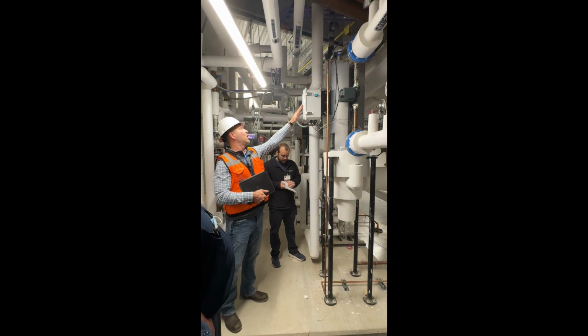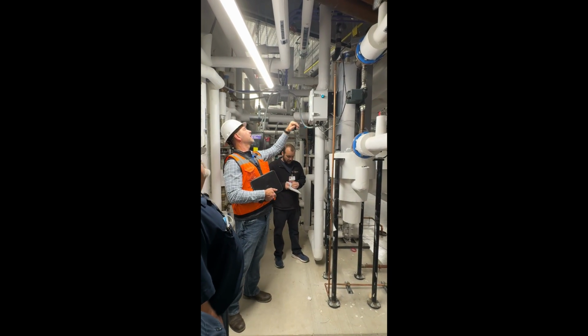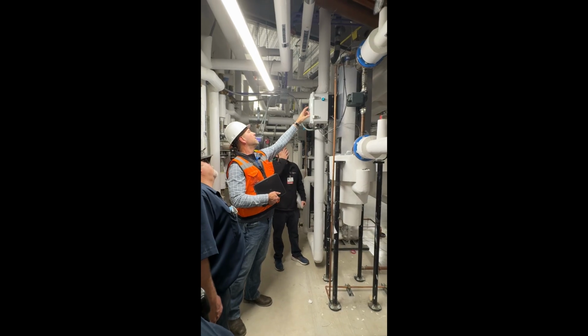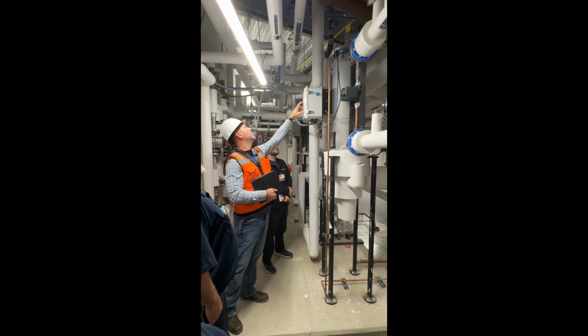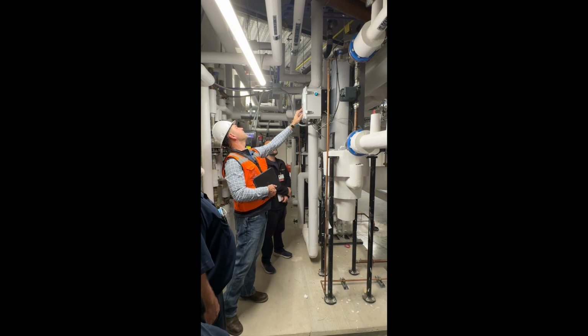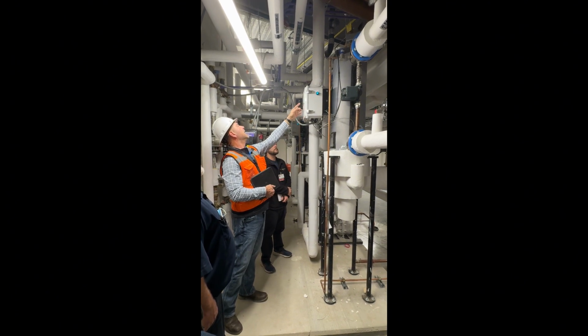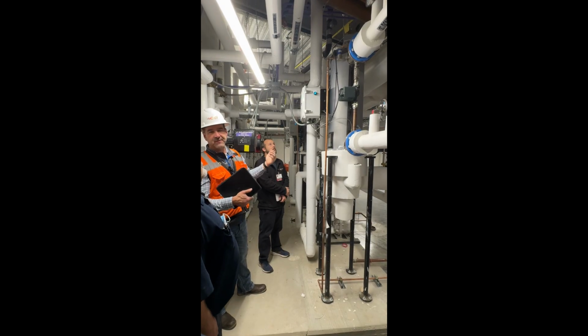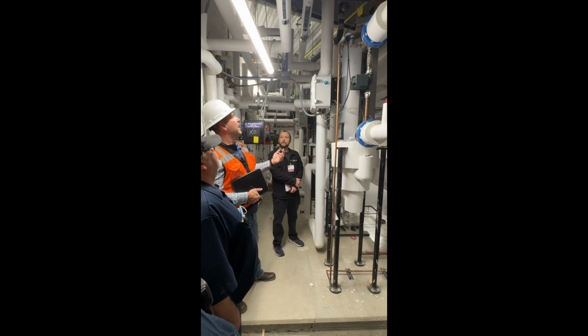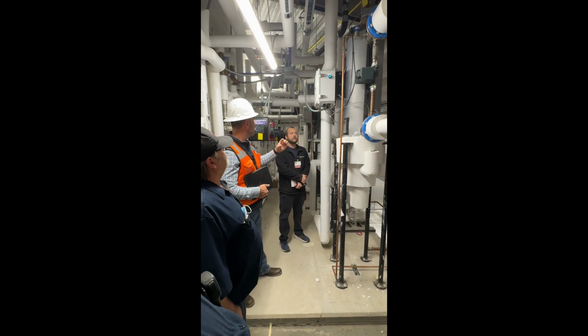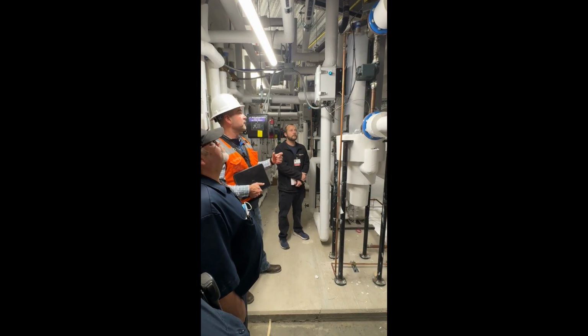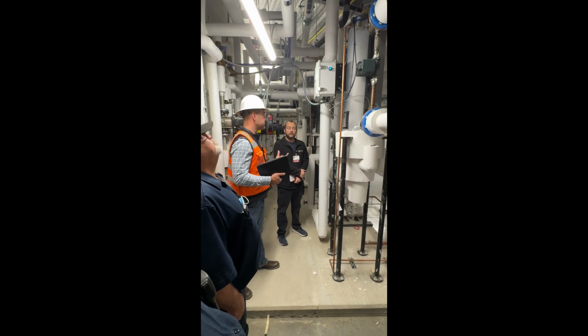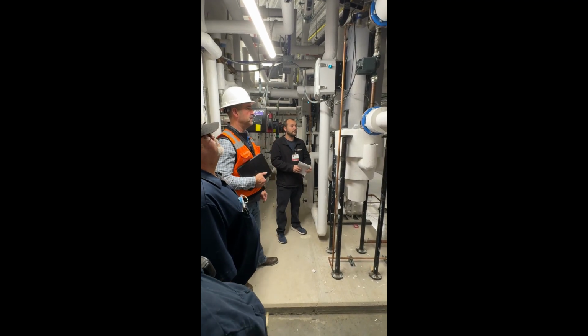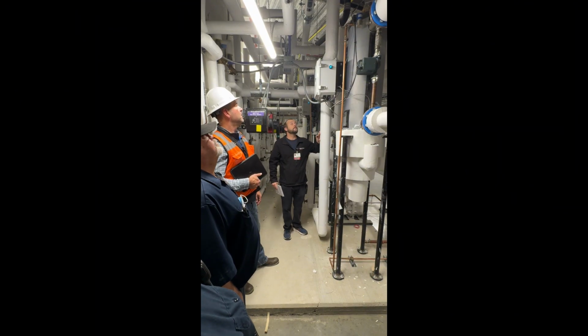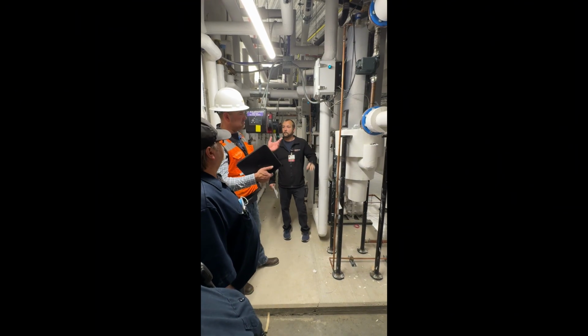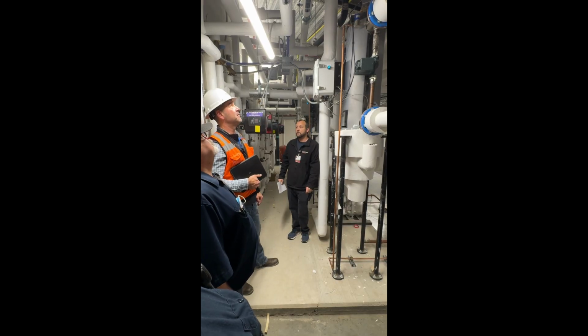Any alarms are going to show on here, and it's kind of hard to see that, but I can't see that. It's showing unit status in green, so that means everything is fine. There's no alarms. If you did have an alarm, that would be red, and it would give you what the alarm code was. Most likely, if anything, it's going to be overtemp for whatever reason. Maybe you've got a valve shut off and it's not able to dissipate that heat. All four of these are identical, so what happens with one happens with the other.